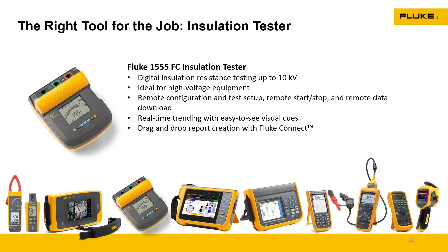We really want to pressurize that insulation and make sure there's no cracks in it, so having a good insulation tester is a key win out in the field. This is part of the commissioning aspect too. The designer came out and designed this system, and there's a tremendous amount of tests and reports that go into it prior to commissioning and putting it into operation. An insulation test is one of those, coming from our combiner boxes especially, going to our inverter, making sure when they buried it there was no damage to the conductors.